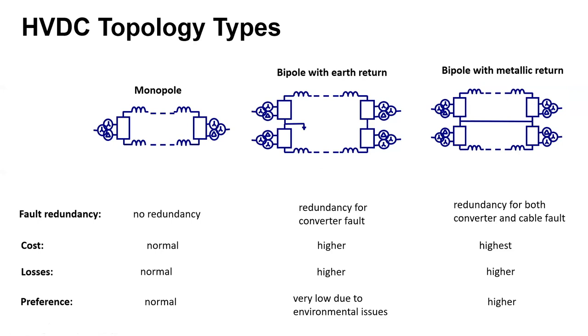You could see the cost for monopole topology is considered normal, whereas with bipole it is highest, because it now has double the converters and one more transmission circuit. But having said this, in terms of technical benefits, bipole's preference is higher than monopole. In terms of economic benefits, its preference is often seen as lower than monopole. So it's really a balance between redundancy and cost when it comes to selecting between a monopole topology and a bipole topology.